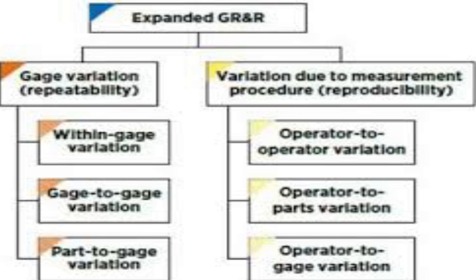When we talk about reproducibility, everything remains the same — same instrument, same location, maybe within the same timeframe — but we are using a different operator, perhaps two or three different operators.